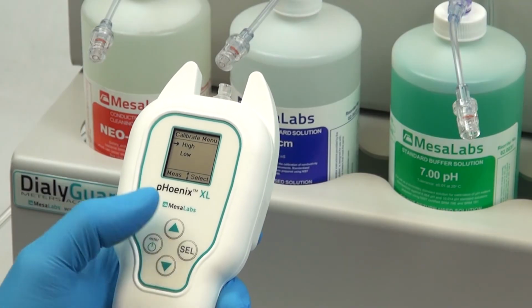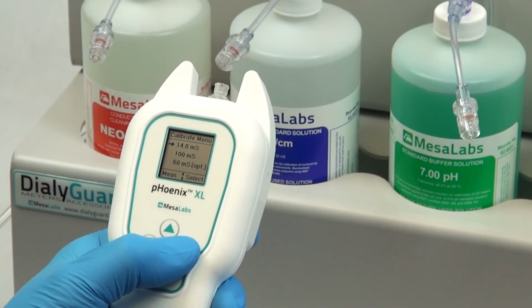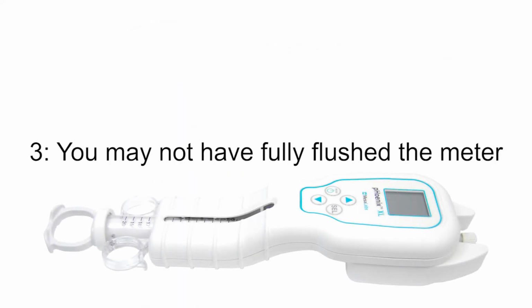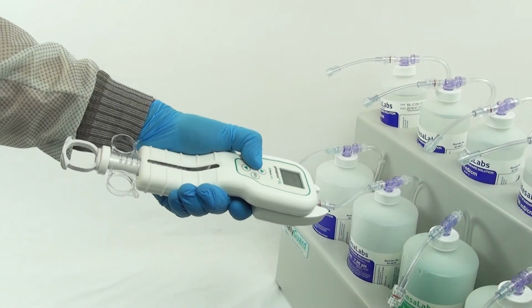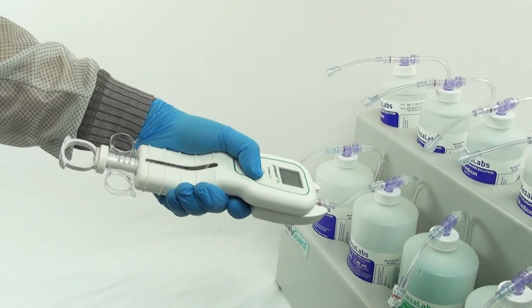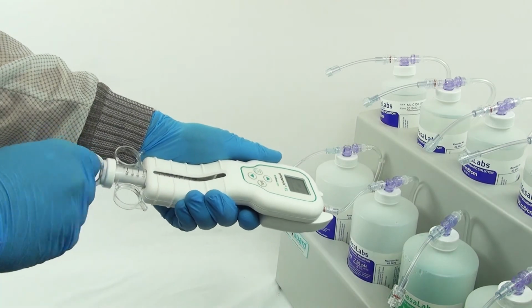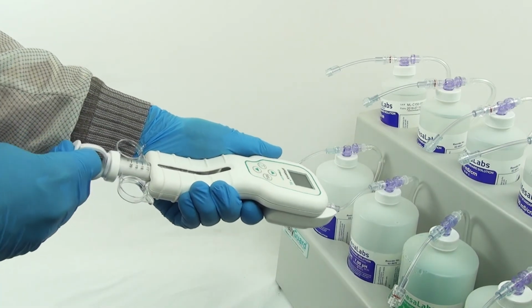Make sure that the solution you are using reflects the calibration mode you are currently in. If a different solution remains in your meter, it may skew your results. Make sure to properly flush the meter before calibrating or verifying solution values.